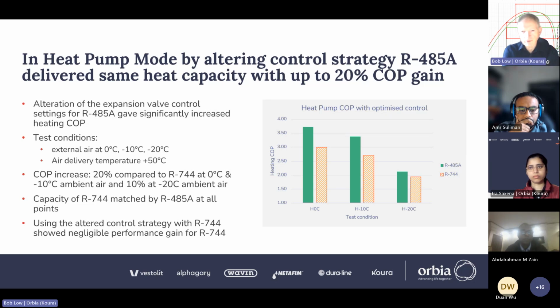And to make sure it wasn't a fluke, we tested the system again with a new control strategy with CO2, and it basically made almost no change to the performance of CO2. I think it gave it 0.5% gain in COP. So it was a good illustration that although the blend can work in a CO2 system, software optimization is useful to get the full benefit of the different thermophysical properties.